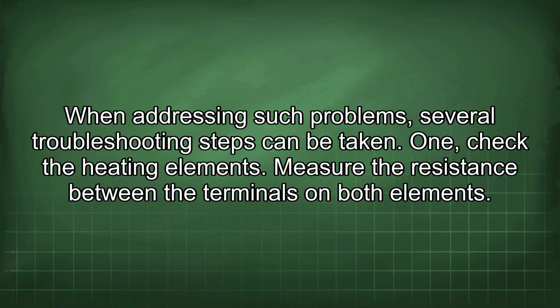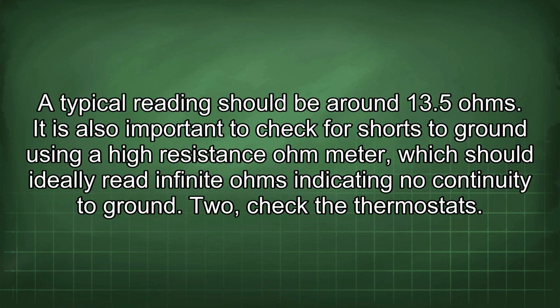1. Check the heating elements. Measure the resistance between the terminals on both elements. A typical reading should be around 13.5 ohms. It is also important to check for shorts to ground using a high resistance ohm meter, which should ideally read infinite ohms, indicating no continuity to ground.